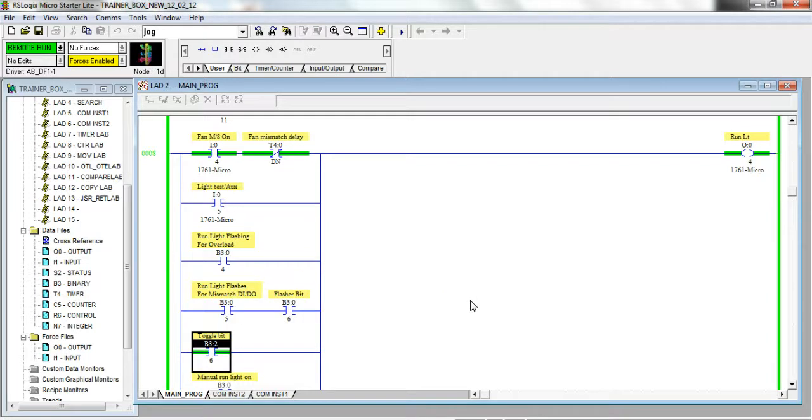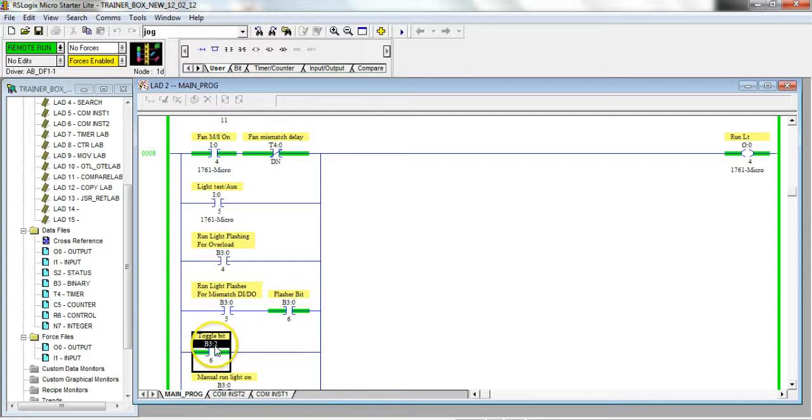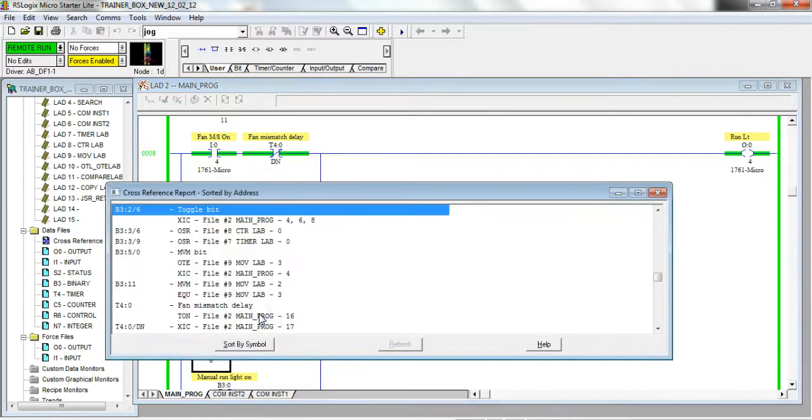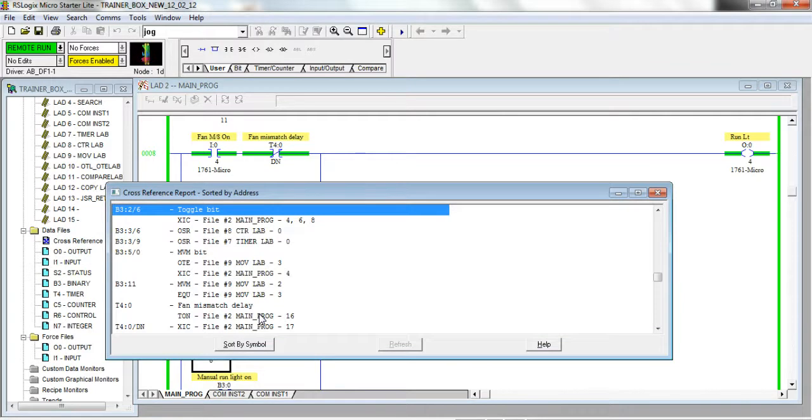And my motor started. So if you were to look at this toggle bit, I'm going to do a right-click cross reference of this toggle bit - which by the way is what you should do before you think about forcing or toggling anything.